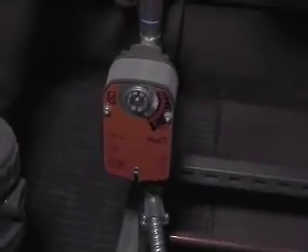Okay. But this is your solid separator. You guys probably already understand the basic concept of it. Whenever a condenser water pump is running, we enable this system to run. So this pump will run through the system, and then this will automatically blow down as needed. It's got its own valve right here if you can see it. They'll have to tell you when it blows down. It's probably off a timer, but it'll blow down as needed.